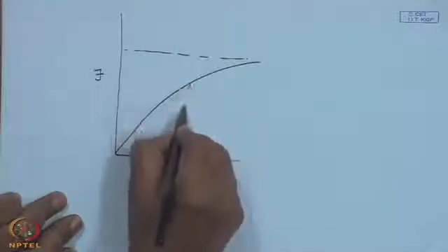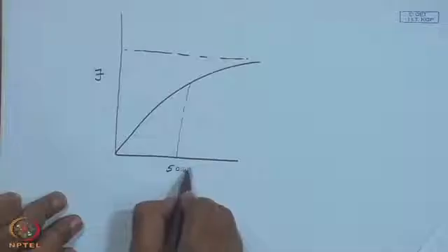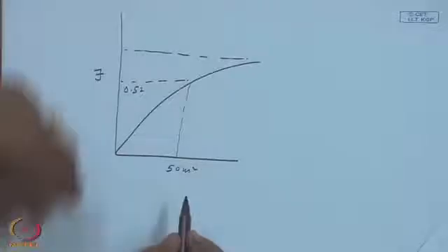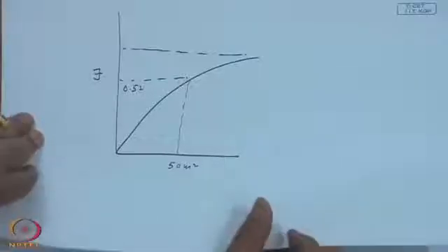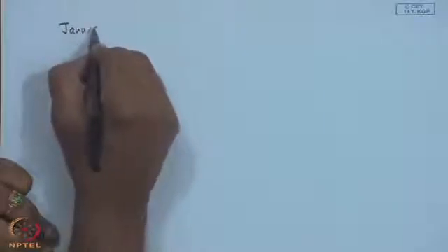If you plot the annual solar load fraction, it may be something like this. For 50 meter square, this may be 0.52. Whereas if you make a monthly calculation, for January it may be less, and for June it may be more, because the solar radiation is more and the load on the system is constant, 12 kilowatts for 12 hours a day. So, I will take the data of January, which you can calculate from the TMY2 also.